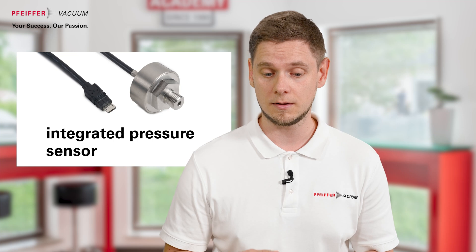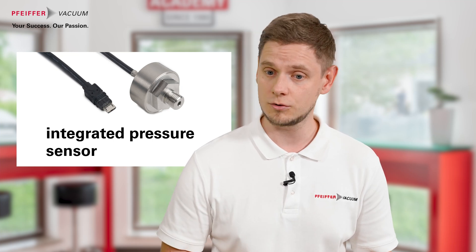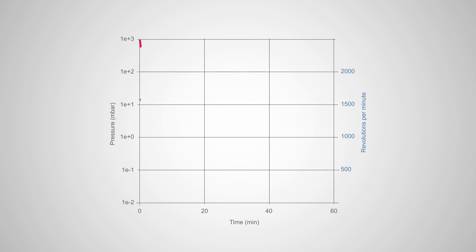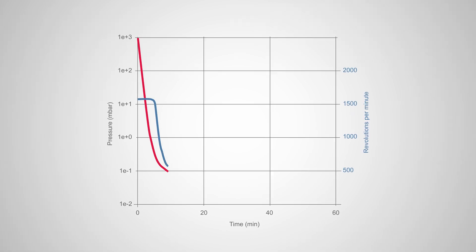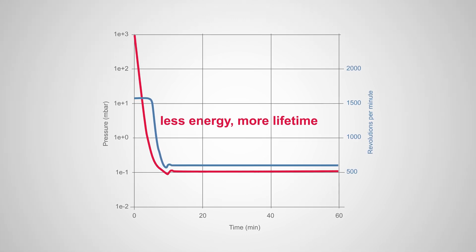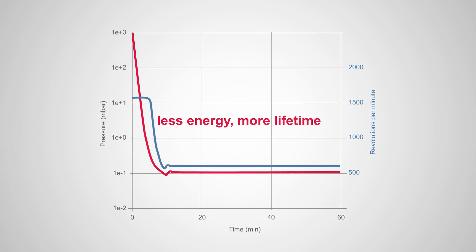That sounds really powerful — and how does this impact, for example, the operation cost for the HiScroll? You can reduce the energy cost of the HiScroll, for example, with the integrated pressure sensor which can activate the pressure control mode. You set a target pressure, and if your customer process doesn't need the ultimate pressure of the pump all the time, the HiScroll reduces its speed automatically. This results in up to 50% energy cost savings as well as increased lifetime.